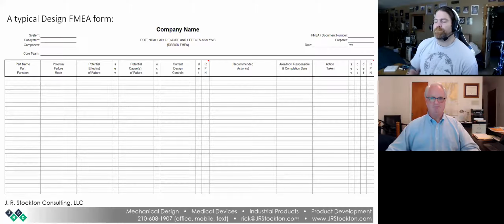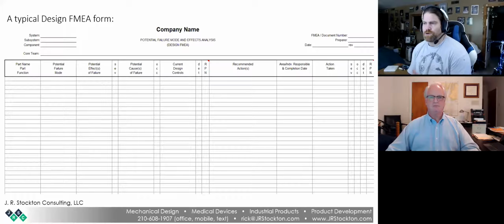And it really depends on how you're going to document these things. But as we get more and more complex devices, I think the whole entire industry is going to eventually come to the realization that an Excel spreadsheet is not the way to do this for an electromedical device or some complex device that has software, because there's too many things to put rows and columns in and to try to document all the verification and validation reports that you need traceability to. You really need a database where you click on a hyperlink and it takes you to the document you want, and you can generate an automated report of some of these things.